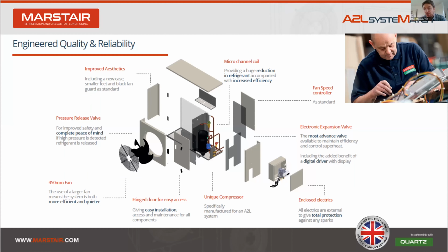So here we have an exploded view. I'm just picking out a few key points. Firstly, the unit has a fitted expansion valve in the condensing unit with the driver and display. It's preset and can run independently like the thermal expansion valve, but you can control superheat much more efficiently. And with a fitted display, it makes it easy to adjust. Second, the externally enclosed electrics box removes all the potential sparking components from the compressor section within the unit. And third, we've used compressors designed specifically for A2L, so in terms of reliability.